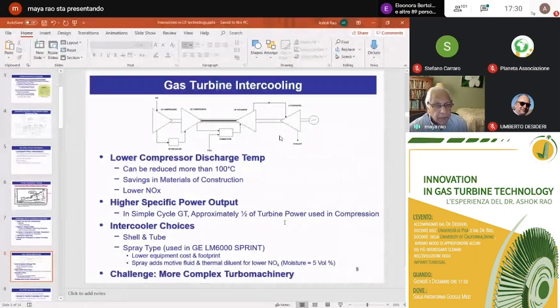Now, there are a couple of ways of intercooling. One is, of course, to have a shell and tube heat exchanger, but the big challenge with that is you need a huge amount of space for it. And shell and tube heat exchangers, when you don't have very good heat transfer coefficients, can be very large and expensive. The other method is to simply spray water, of course, it has to be high quality water, into the airstream leaving the low pressure compressor.